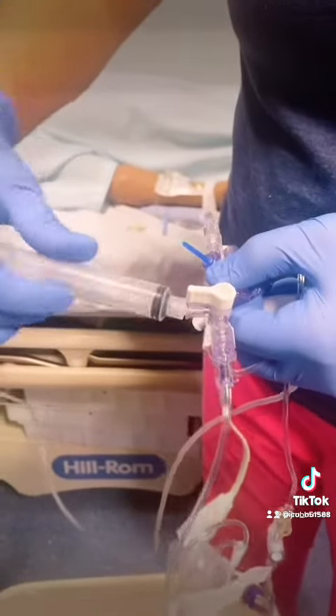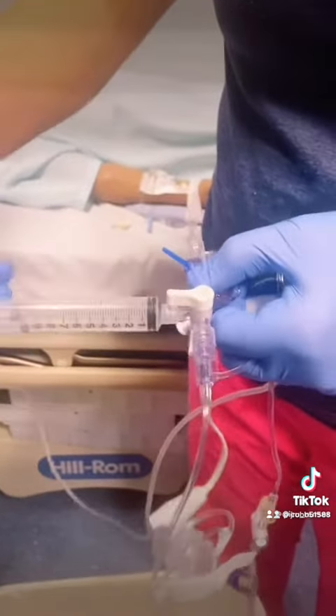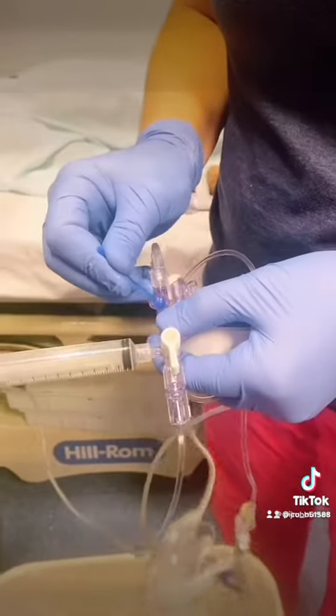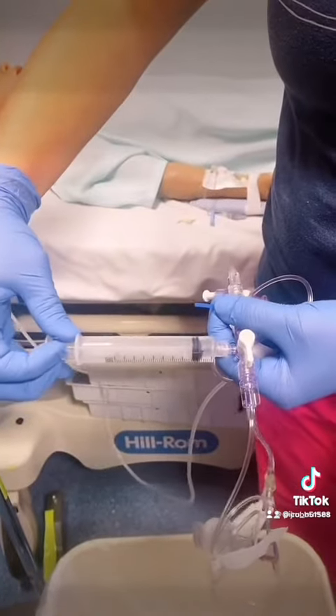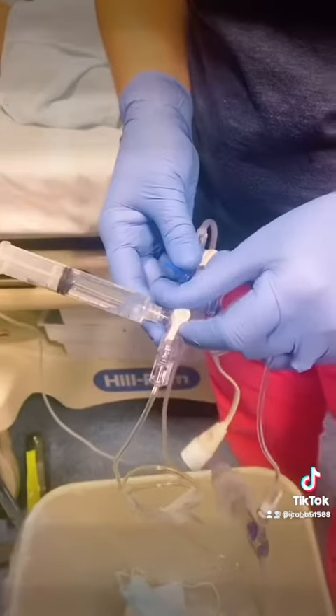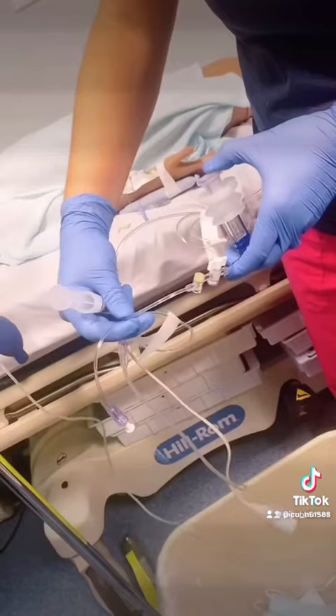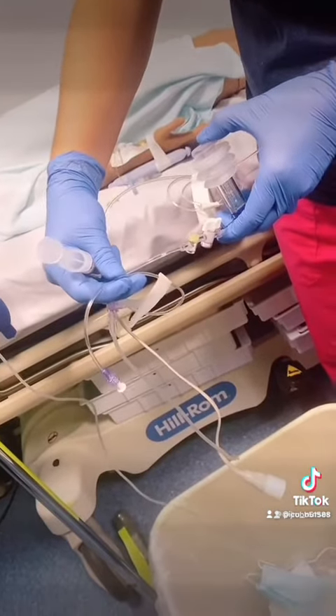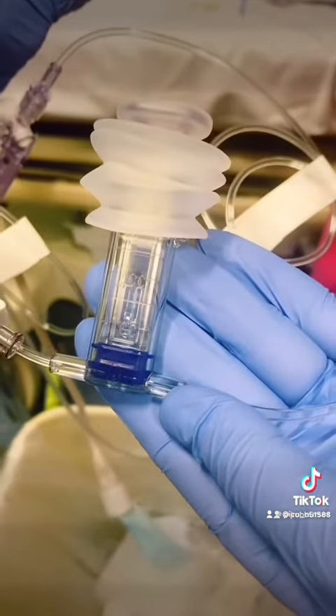Here, you're going to attach it to the port that you just primed. You're going to turn off to the patient, and then you're going to prime that by pulling the blue pigtail. The first time you do it, you might need to help it a little bit, but after that, it should prime pretty much on its own when you pull the blue pigtail. Make sure to turn off to the syringe so it's back open. Then push down on the reservoir to lock it in place and the blue plunger to the bottom.